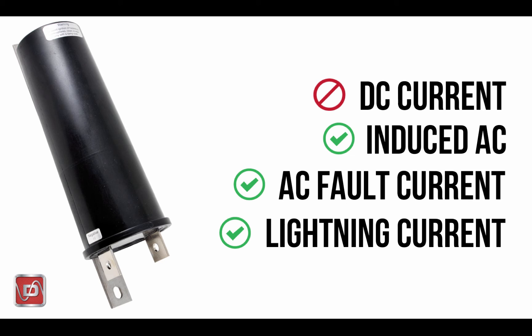Blocking the conduction of DC current and conducting induced AC aren't the only functions decouplers must be able to perform, however. They also have to handle AC fault and lightning effects. They turn on during a lightning strike or an AC fault to safely handle the event, then go back to DC isolation and AC conduction mode.